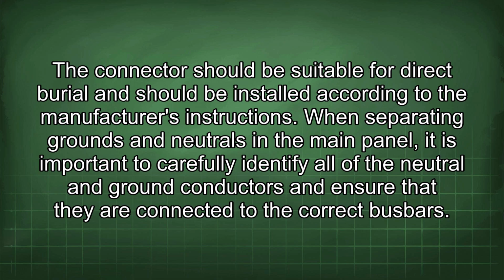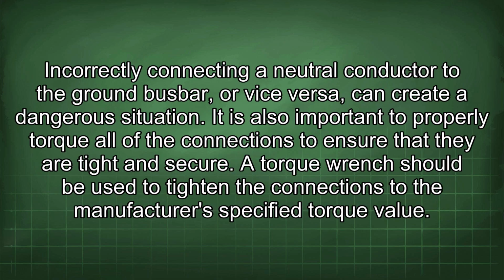When separating grounds and neutrals in the main panel, it is important to carefully identify all of the neutral and ground conductors and ensure that they are connected to the correct bus bars. Incorrectly connecting a neutral conductor to the ground bus bar or vice versa can create a dangerous situation. It is also important to properly torque all of the connections to ensure that they are tight and secure. A torque wrench should be used to tighten the connections to the manufacturer's specified torque value.